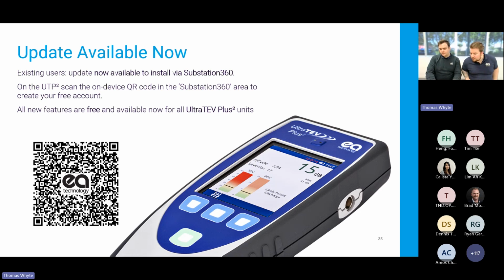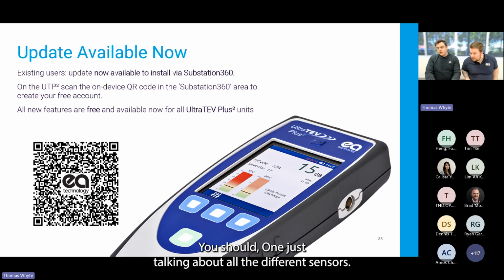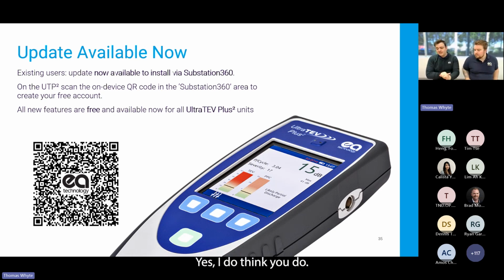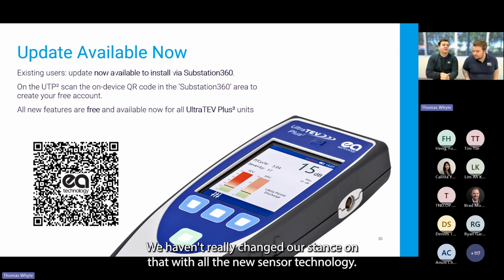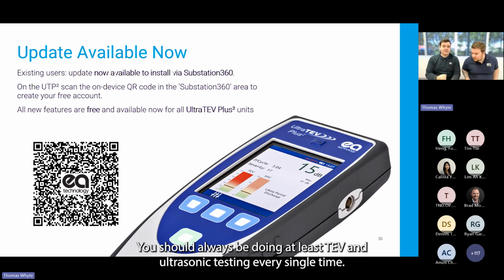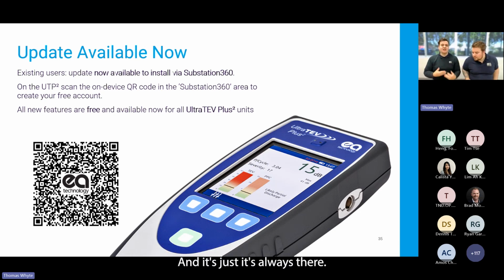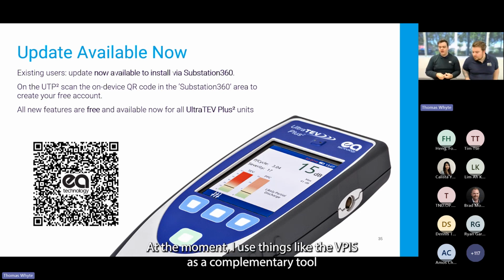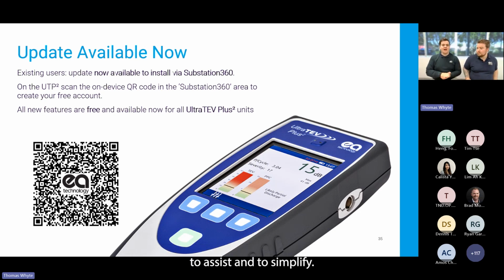Talking about all the different sensors, should you do every test every time? Yes, I do think you do. We haven't really changed our stance on that with all the new sensor technology. You should always be doing at least TEV and ultrasonic testing every single time, because they're always there and different defect types can be found with it. At the moment, I use things like the VPIS as a complementary tool to assist and simplify, but it is still rather new, and TEV and ultrasonic are still the bread and butter of this type of testing.